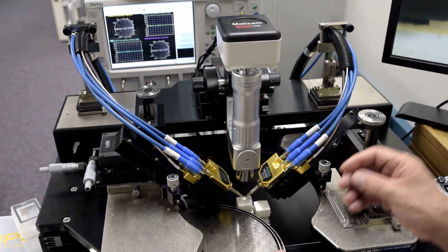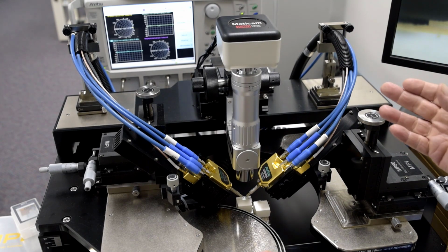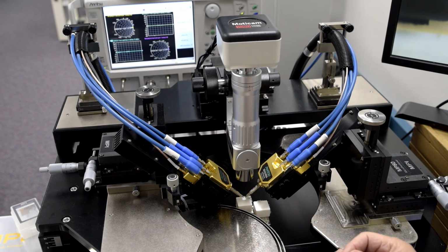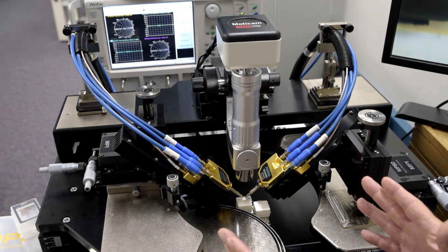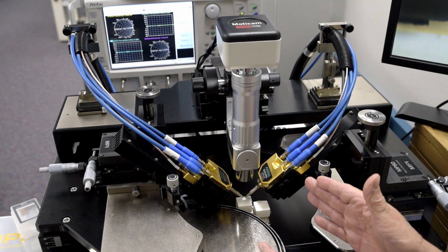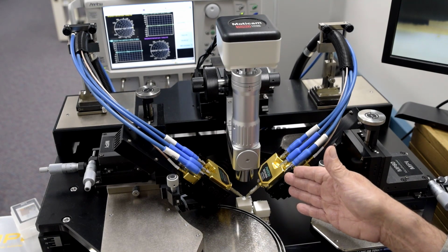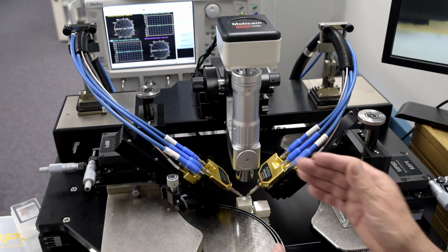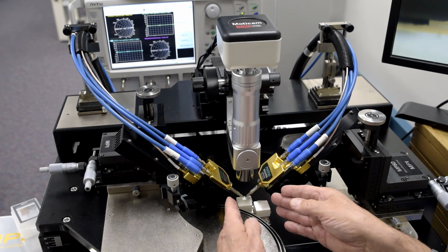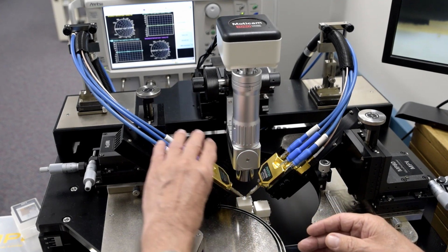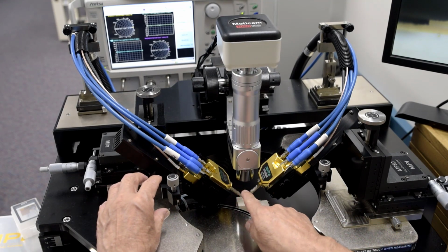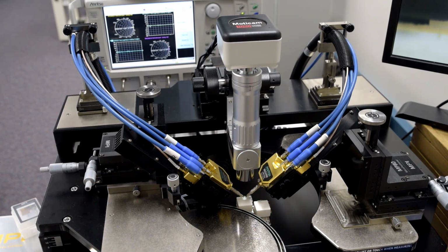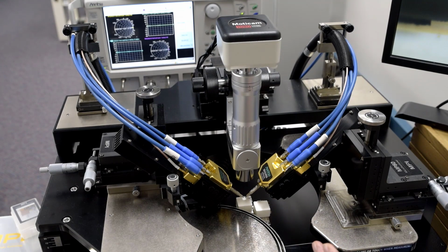Now the key for going up into the broadband millimeter wave frequencies is to optimize the system installation for best performance in terms of raw directivity, stability, etc. And so obviously you would want to eliminate the test port cables from the test port of the module to the probe. So for instance, if we didn't have a direct connect capability like we have here, we would have to mount the modules back on the platen and connect to the probe using cables. And of course, cables in this case will have an impact on the overall stability in terms of temperature and time. So with these modules, we have an interface cable connected going back to the VNA.